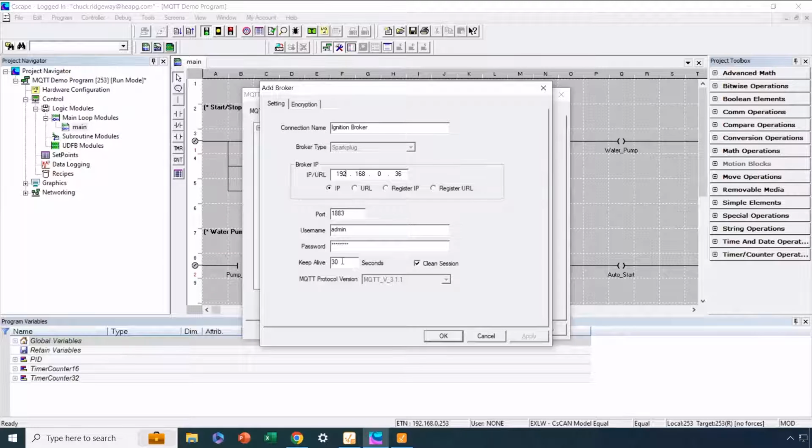Now, what is keep alive? Well, one of the things that Sparkplug does is it defines a way that subscribers to data can know that the publishers of data may be down or that the data that they're looking at is invalid. So one of the ways that happens is through a keep alive. As the OCS that's publishing data to the broker, I'm going to be sending data periodically, and we haven't decided what data yet, but we'll cover that in a minute.